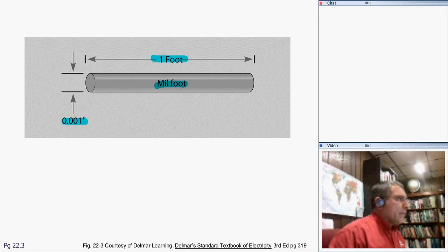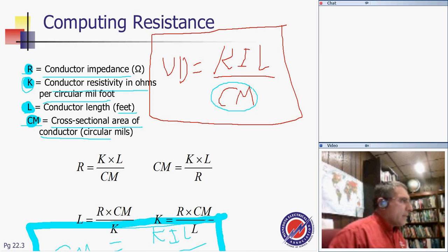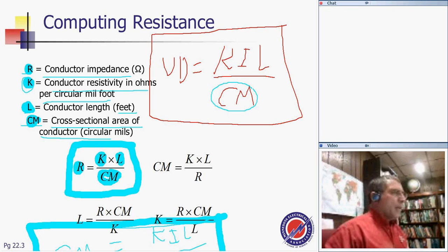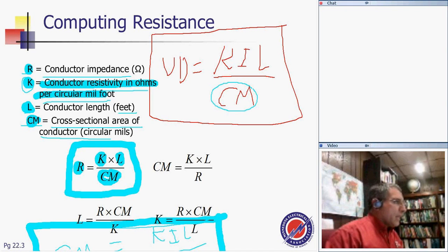I'm going to go back to this example. What it tells you is this one here at the top. The resistance of the conductor is a function of K, which is the resistivity for that particular conductor material, like copper or aluminum, multiplied by the length, divided by the cross-section area of the conductor. What does that mean, guys? It means the longer the conductor, the more resistance. The larger the size of the conductor, the smaller the resistance, and it stays constant based on temperature and that particular material, copper or aluminum. As you can see, these are basically three forms of the same thing.